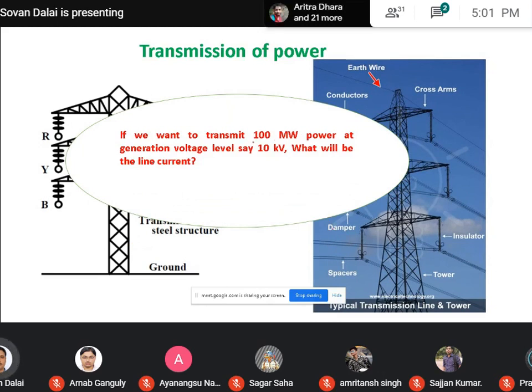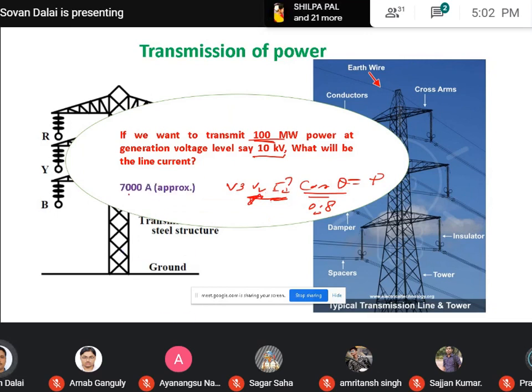Suppose you want to transmit 100 megawatt of power. This is a case study just for your knowledge. If the transmission voltage level is 10 kilovolt, what will be the line current? All of you know that three-phase power is represented as √3 VL IL cos theta, which equals the power. If the voltage level is 10 kV, and for simplicity you consider the power factor to be 0.8, we want to find IL. Replacing cos theta by 0.8 and VL by 10 kV, the current rating for transmitting this power is in the range of 7,000 ampere.